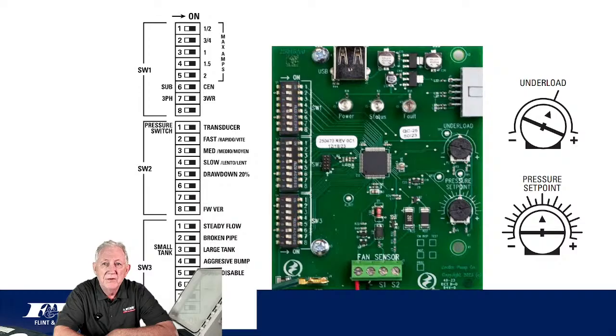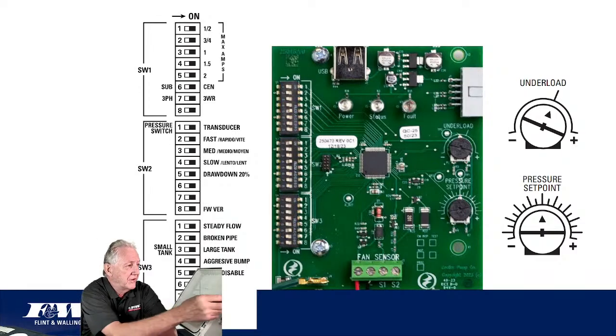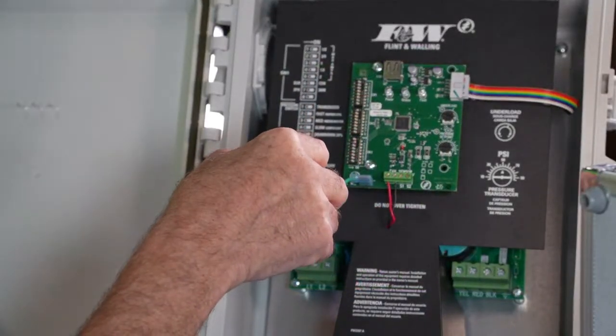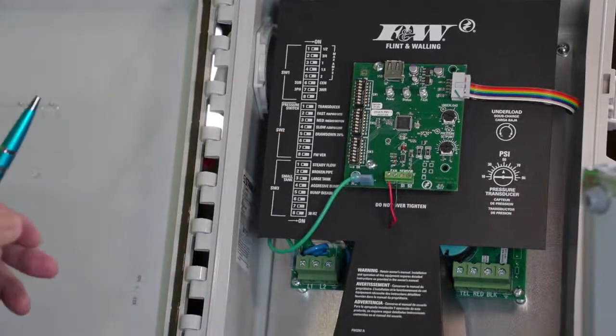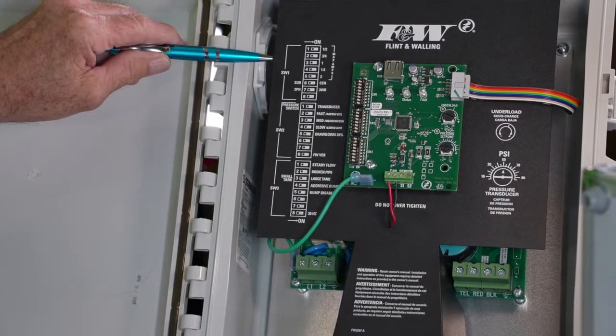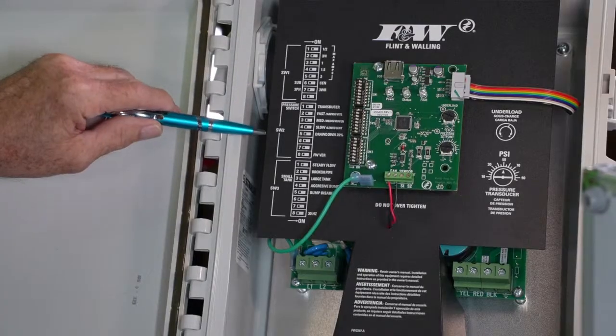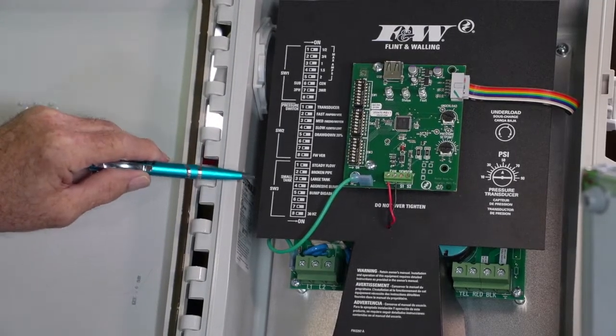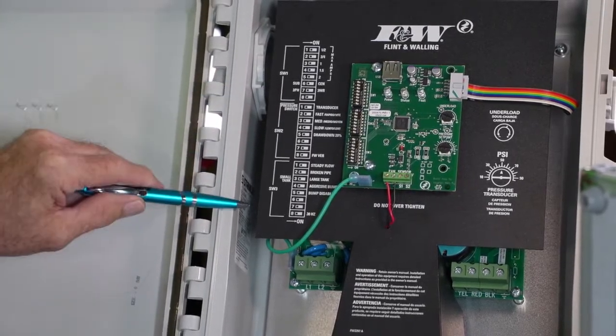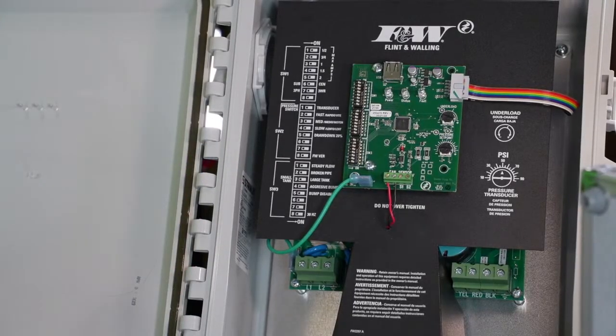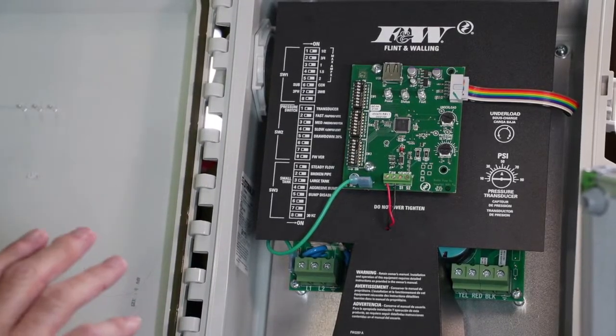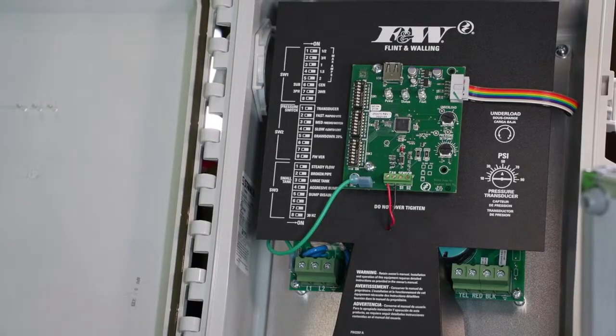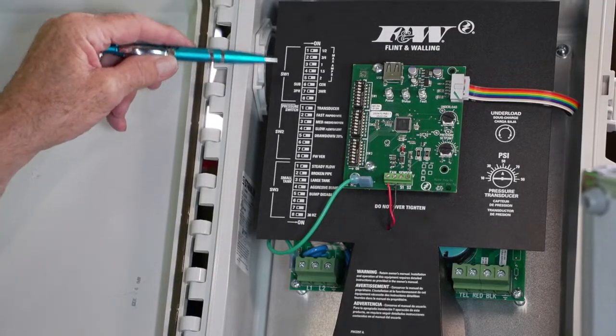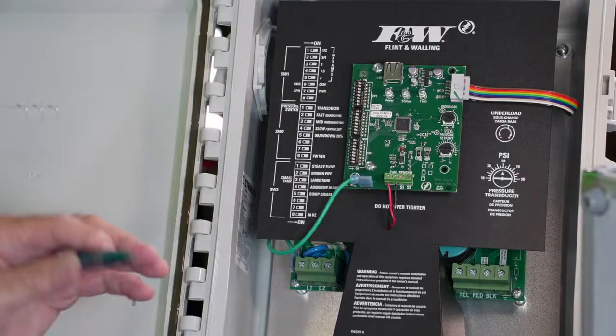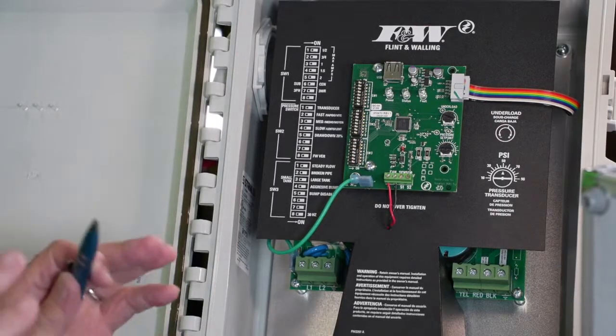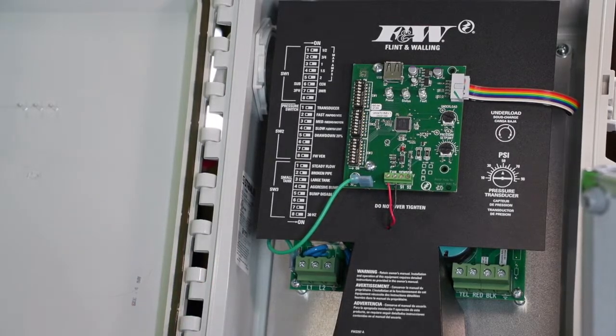All right, so the only other thing on the inside of the drive is this bank of dip switches over here on the left-hand side. There's 3 banks, okay? SW1, SW2, and SW3, all right? So switch bank 1, switch bank 2, switch bank 3. Let me clarify these 3 banks real easy for us, all right? That first bank, this bank up here, that has only to do with the pump motor, right? That's all it has to do with is the pump motor, period.